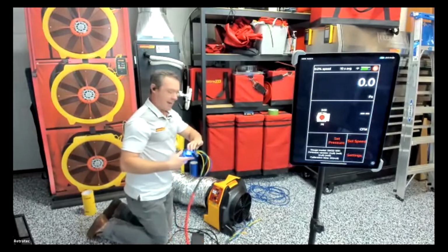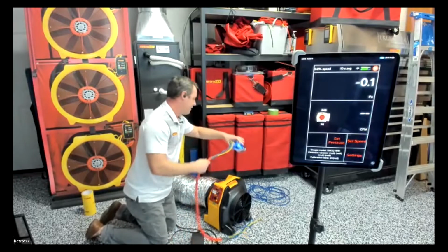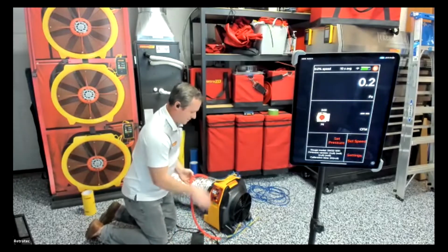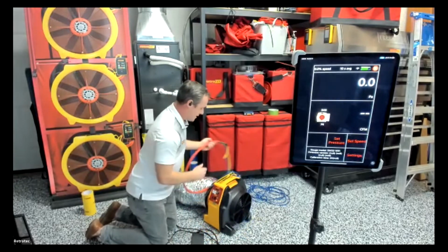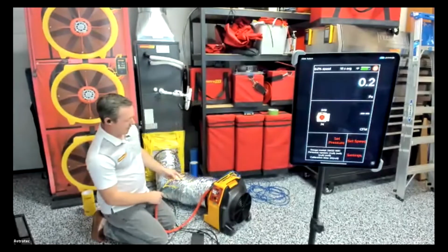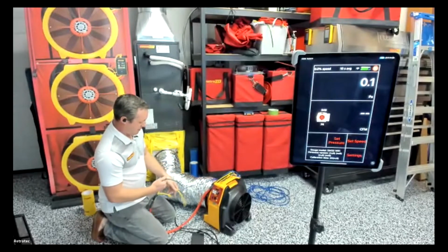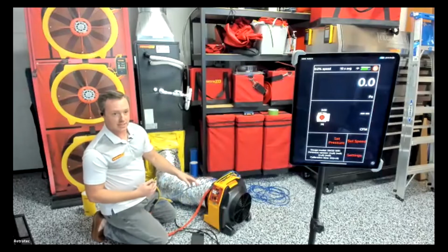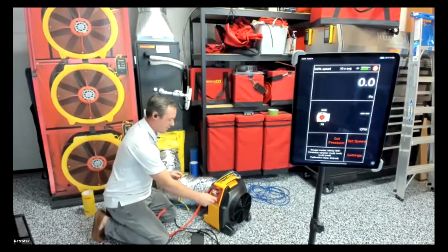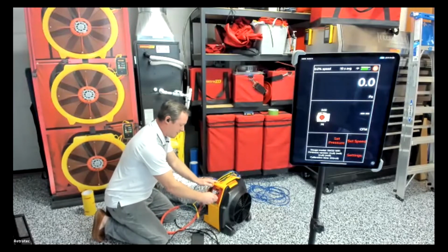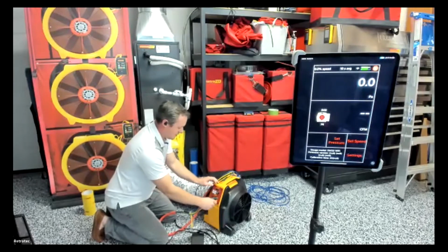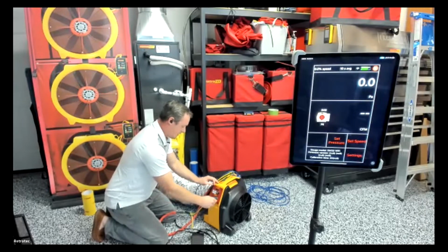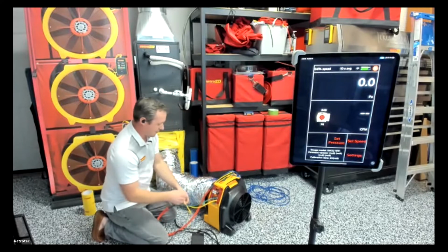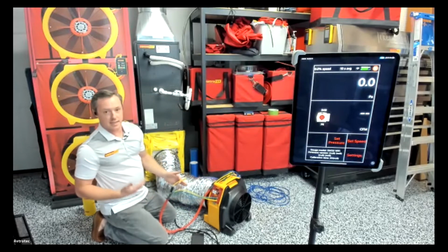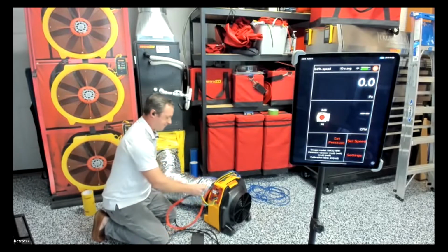And then we're going to do the exact same thing on the fan side - slap the manometer back there. As I mentioned, yellow and green read fan pressure, so there's a matching yellow and green port on here. We'll pop those on there like so. And then the other end of that data cable plugs into the fan as well. This allows the gauge to control the fan.